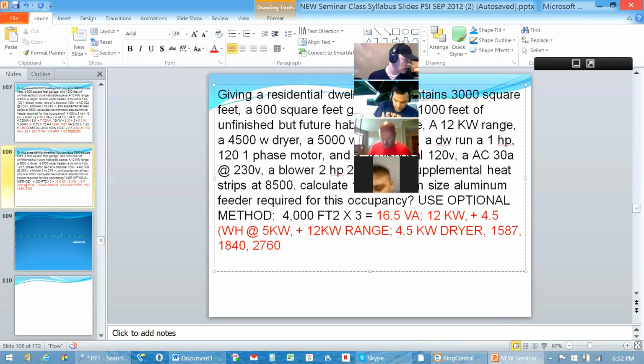On page 73, what? On page 73, oh, I got you. Yeah, on the left-hand column at the bottom, when you're done with step 4, B4, you want to make yourself a note to stop there. Don't include the air conditioner heating yet. Go back to the top of B, where it tells you that we're going to take these values all together and take one big D rate against the whole mess. But we're keeping the first 10,000 now instead of 3,000 at 100%.